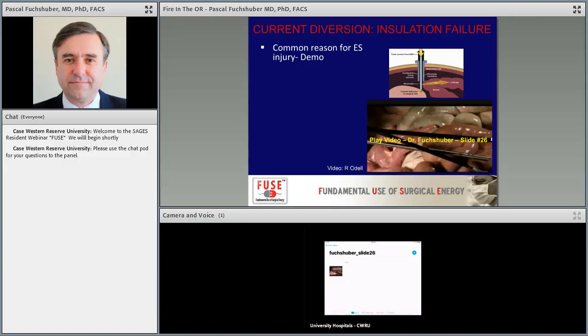It is thought that it's rather common that insulation failure leads to burns in laparoscopic procedures and other procedures. It's the smaller breaks in the instrument's insulation that lead to the dangerous situation. And I go back to what Dr. Madani said about the density, current density. The smaller the break, the higher the leaking current density, the more energy per square inch or millimeter is delivered, and the higher the injury rate is.